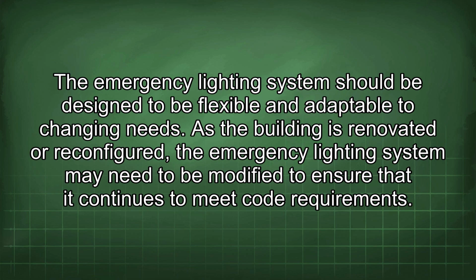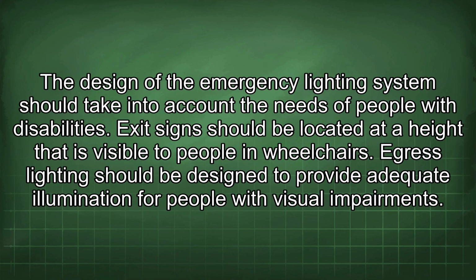The emergency lighting system should be designed to be flexible and adaptable to changing needs. As the building is renovated or reconfigured, the emergency lighting system may need to be modified to ensure that it continues to meet code requirements. The design of the emergency lighting system should take into account the needs of people with disabilities. Exit signs should be located at a height that is visible to people in wheelchairs. Egress lighting should be designed to provide adequate illumination for people with visual impairment.